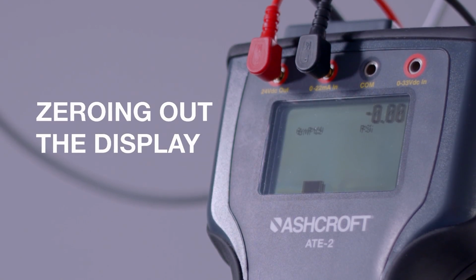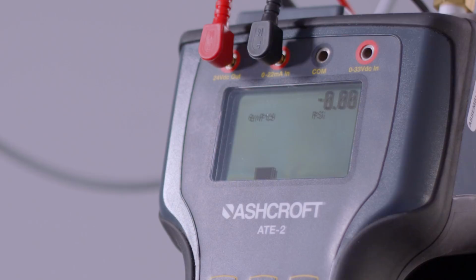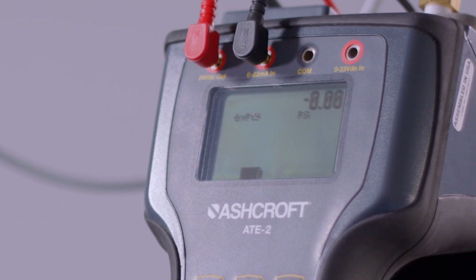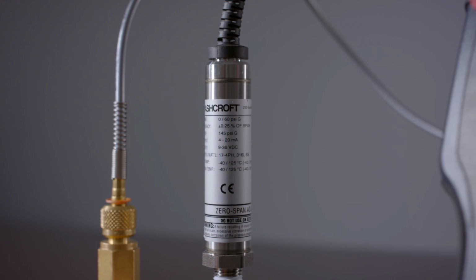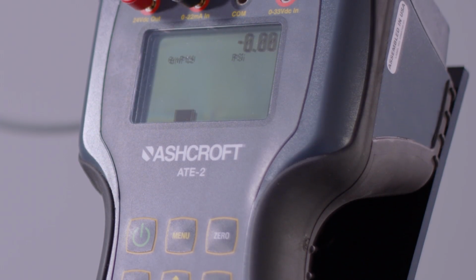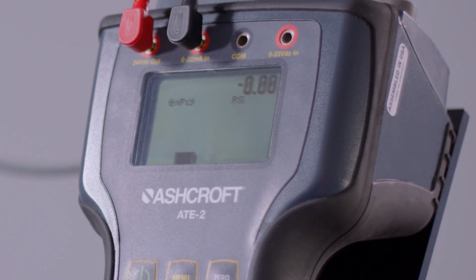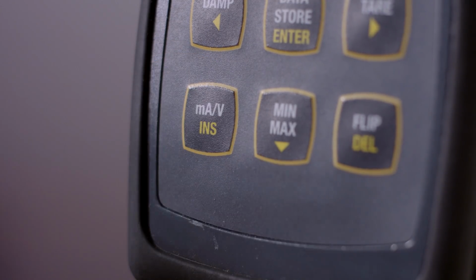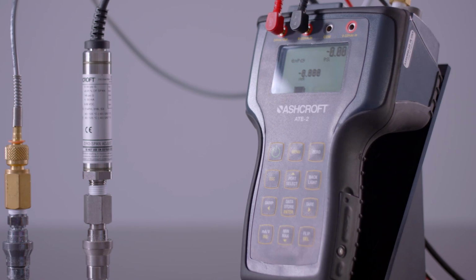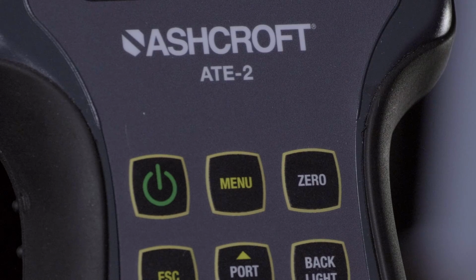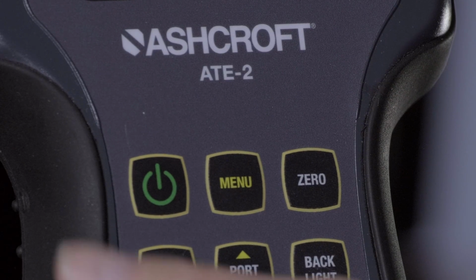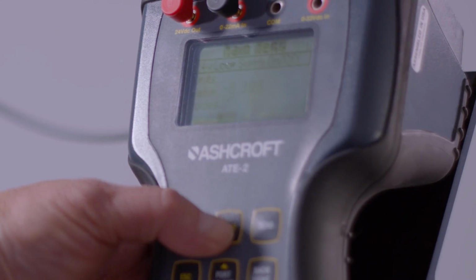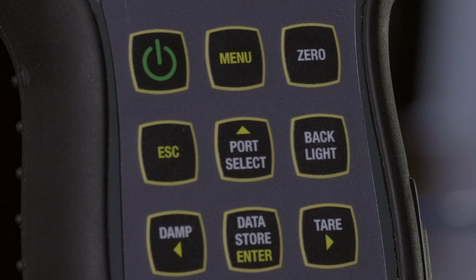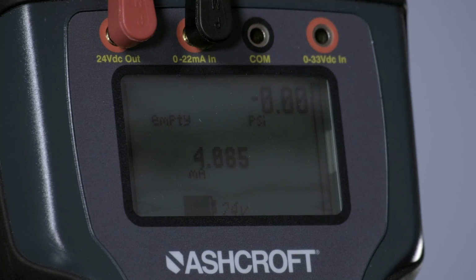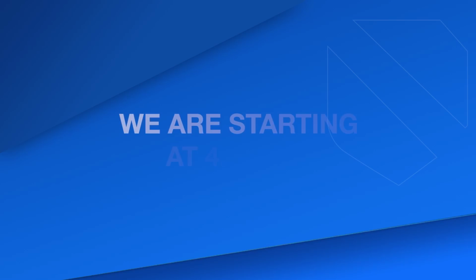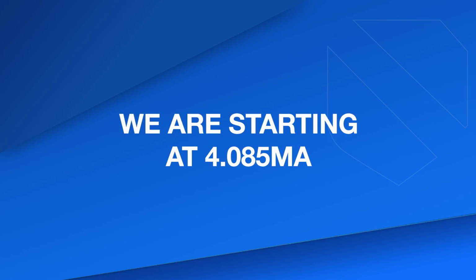To begin, let's zero out the display and make sure we're viewing the correct measurement. As we are providing power to the transducer from our handheld calibrator, we will now turn on the loop supply voltage function. First, we'll turn the milliamp volt output on so we can see the reading from the transducer. Now, we will activate the loop power feature on the handheld calibrator by pressing Menu, highlighting the loop supply item, and pressing Enter. We now have a reading from the transducer at 0 psi. Note that we are starting at 4.085 milliamps.